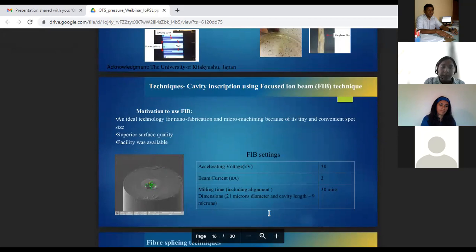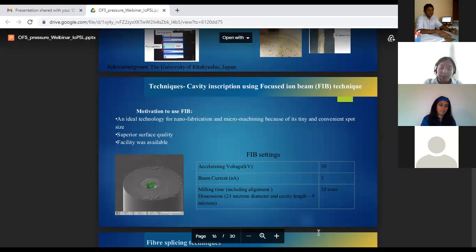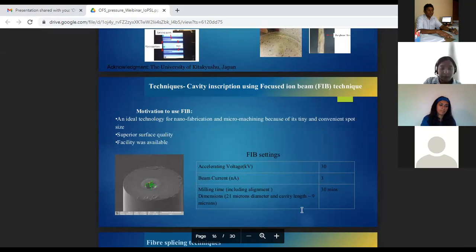Focused ion beam milling was used to form the cavity as one technique because FIB provides the most precise and maskless micro and nano fabrication tool. In the focused ion beam technique, a highly focused gallium ion beam column is used to mill or to image a sample inside a vacuum chamber. Typically, its spot size is around 10 nanometers, which provides high precision in micro and nano fabrication. Most of these FIB systems are integrated with an electron beam, as in a scanning electron microscope, which allows imaging during the processing. Can I have the next one, please?